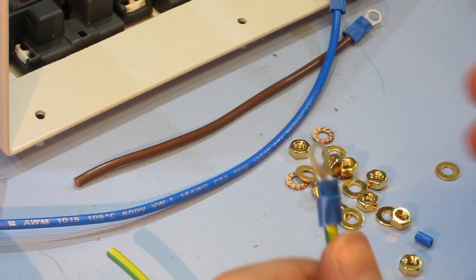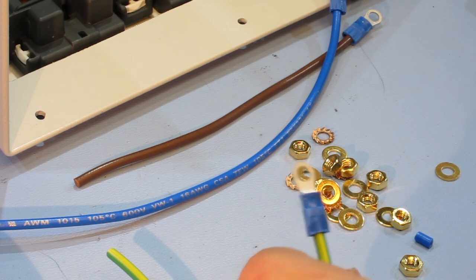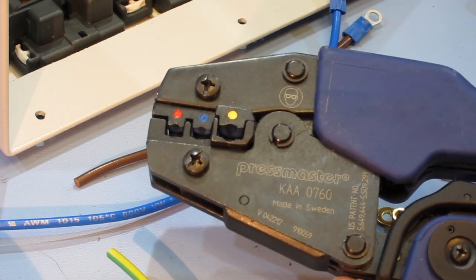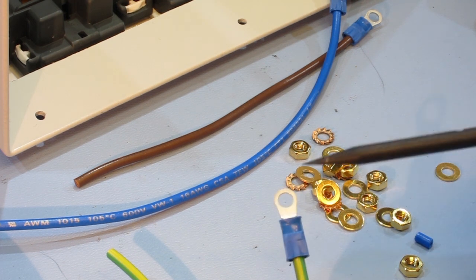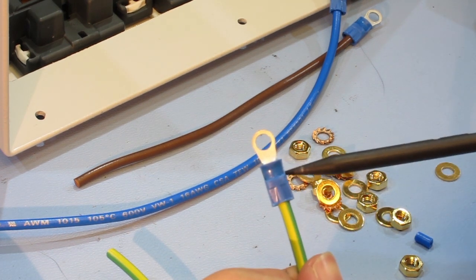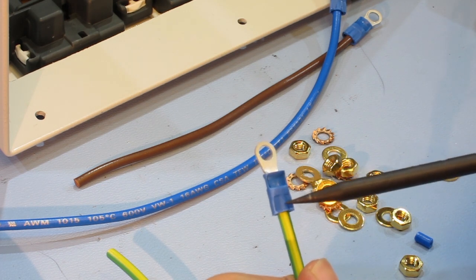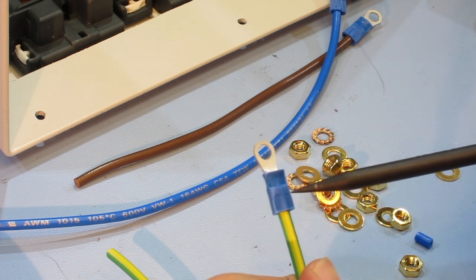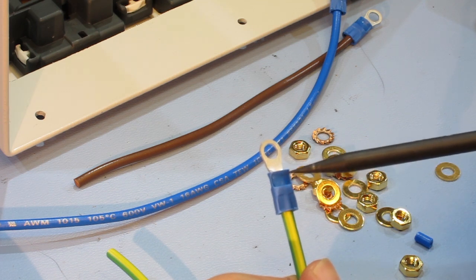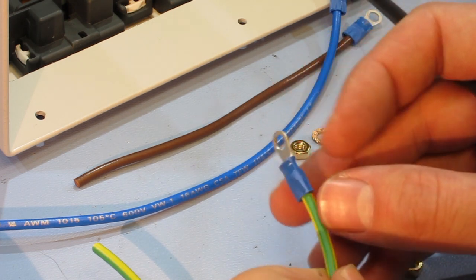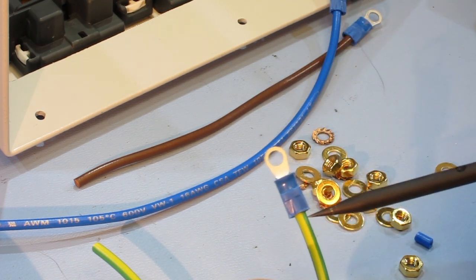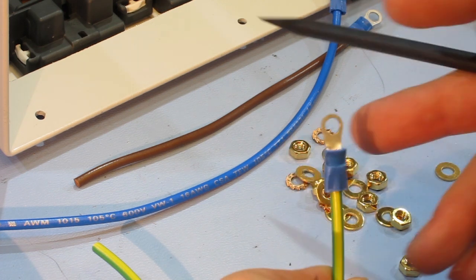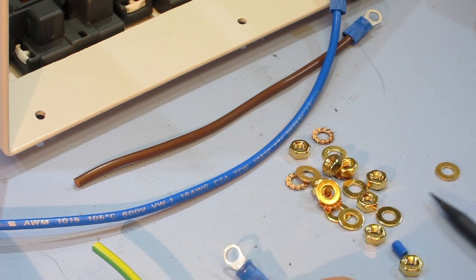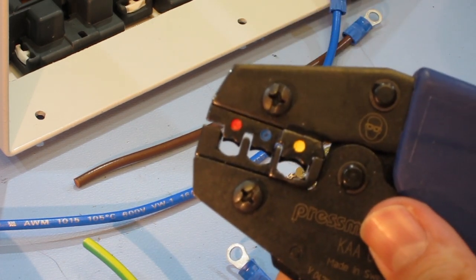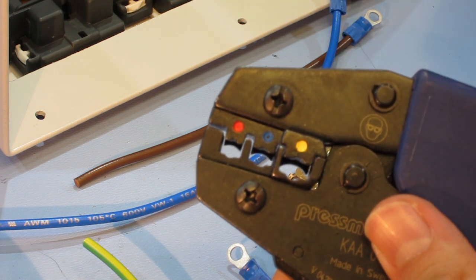So when you're using these crimps, you should make sure that you're using a good quality ratchet crimp tool, but also there's a correct way to insert the crimp into the tool. You can see possibly on the camera just the bottom part of the crimp has a slightly different pattern to the top, and also the top part of the crimp is compressed slightly more than the bottom part, which is just providing strain relief onto the PVC sheath, whereas the top part's actually crimping the copper onto the lug.